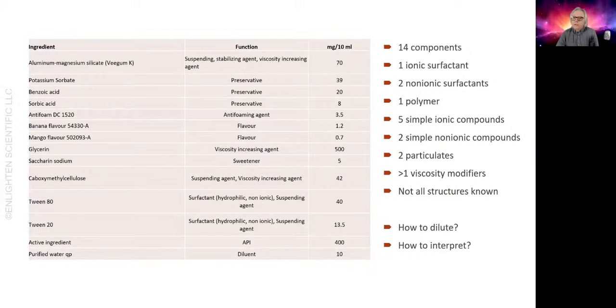Diluting can affect surface equilibria. If a surfactant you're using is weakly adsorbed onto the drug particles, then on dilution it may desorb and your measured zeta potentials may be completely unrelated to the zeta potential of the original product. So do you try and measure the zeta potential of the diluted particles at the original concentration of surfactant, or do you dilute the surfactant as well? There's no simple answer to that.